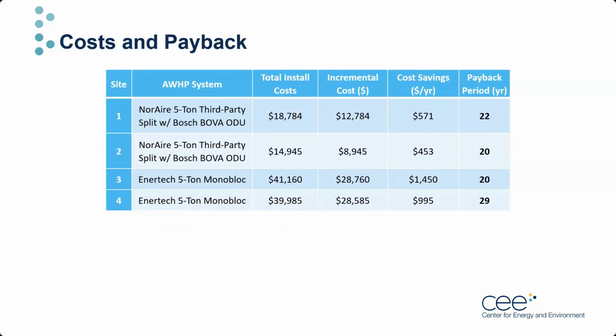Here are the estimates for cost and payback. The heating-only NorAire systems were the cheaper of the two systems to install, with total upfront costs of about $15,000 and $19,000. Compared to the baseline electric boiler replacement of about $6,000, these installations will have a payback period of about 22 and 20 years.